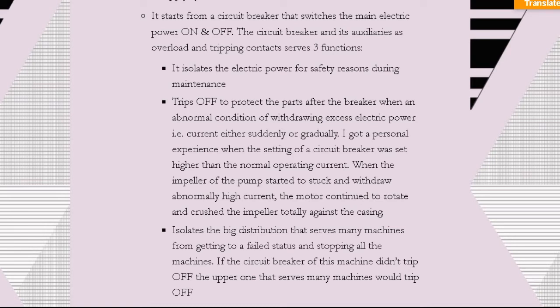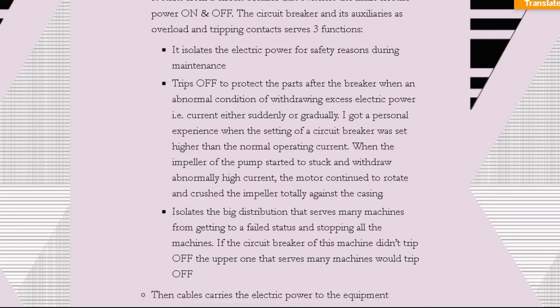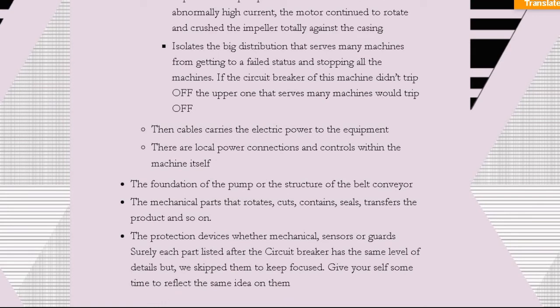Also, it isolates the distribution behind this breaker, so it protects the other breakers on the same line feeding other machines, so they do not all fail due to a failure of sub-equipment of this breaker itself. Also, there are the cables between the main breaker and the skid or the conveyor, and there are the local power connections and the sensors for the protection and so on. Every one of these can stop the rotation of the motor, and stopping the rotation of the motor stops the function.